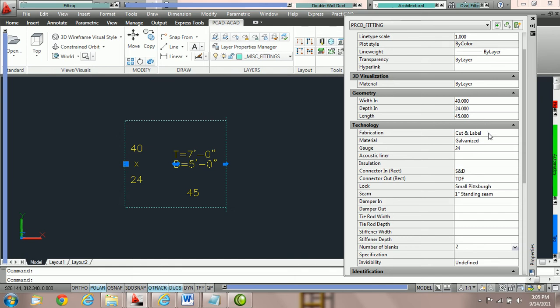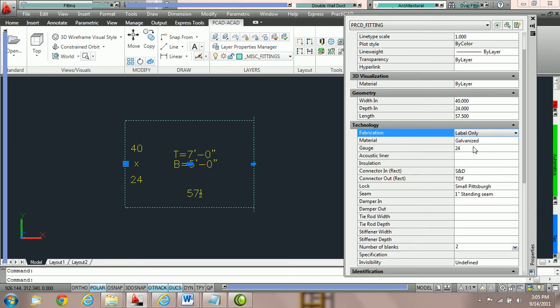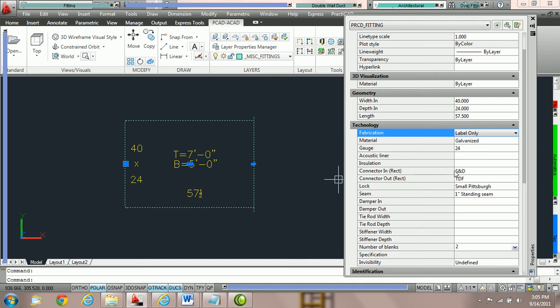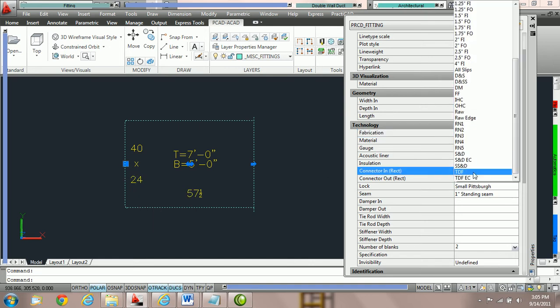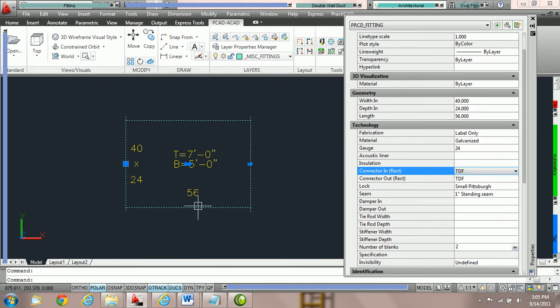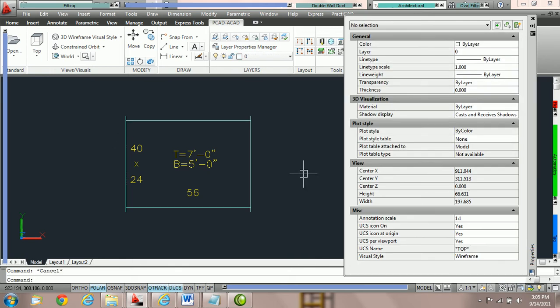Now we're going to switch the fitting to label only. Note the second we switch it, PractiCAD has readjusted the length of the fitting. The reason it's currently at 57 and a half is because we have half TDF and half slip and drive — we're losing two and a half inches from a 60-inch default stock length, two inches for the TDF and a half inch for slip and drive. We're going to switch them both to TDF, and notice the second we do that the length adjusts.